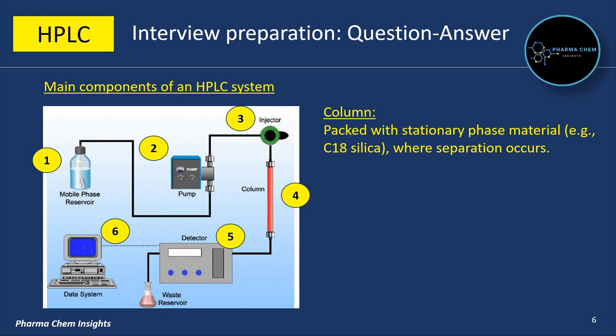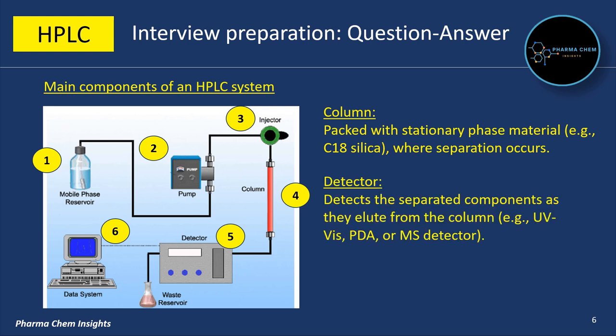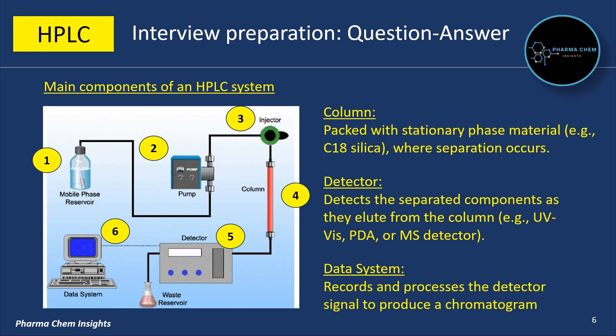The column is also called the heart of the HPLC system. It is packed with stationary phase material such as C18 silica, where actual separation occurs. The detector detects the separated components as they elute from the column — examples include UV-Visible detector, PDA detector, or MS (mass spectrometry) detector. The data system records and processes the detector signal to produce a chromatogram.